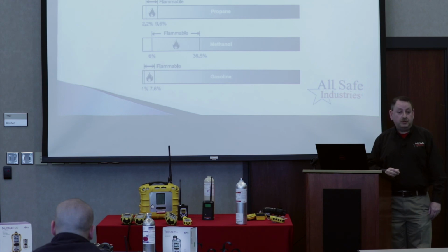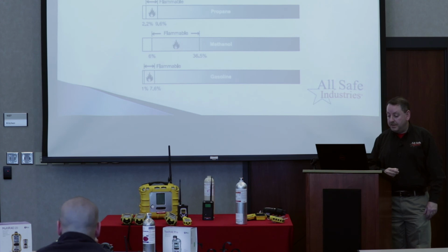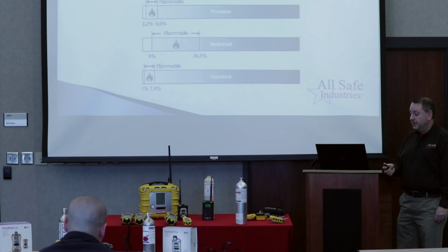We also have methane, which you'll probably run into most frequently. Methane, also known as natural gas, that's what most homes are using to power their furnace or their heaters. And so 5.3% as the lower explosive limit to 15% as the upper explosive limit. You can see the upper and the lower on propane, methanol, and then see down there at the bottom gasoline. And of course we knew this also, gasoline is flammable. And so it becomes flammable very quickly. So let me show you another video. And this explains how your LEL sensor is actually working. So let's see if this one works for us.